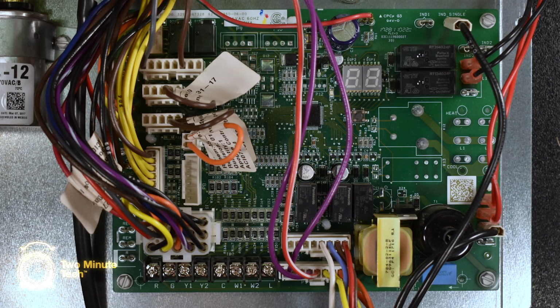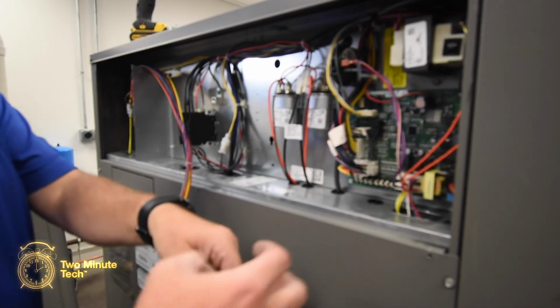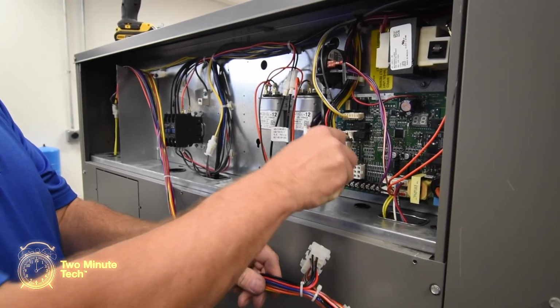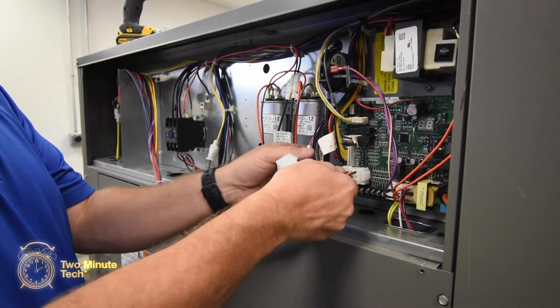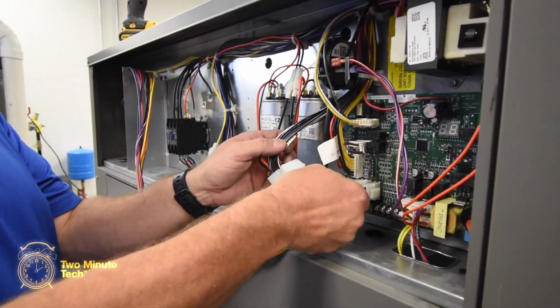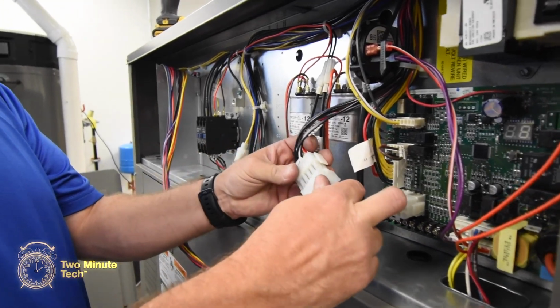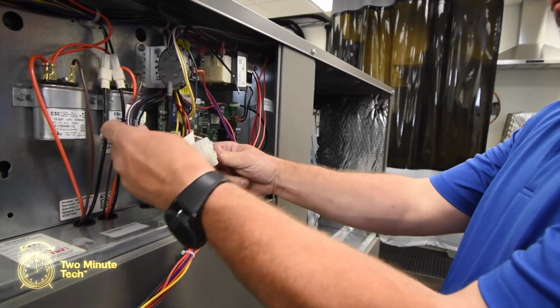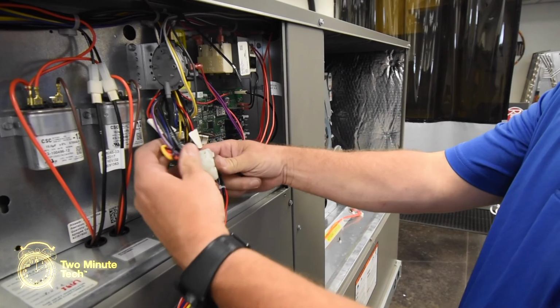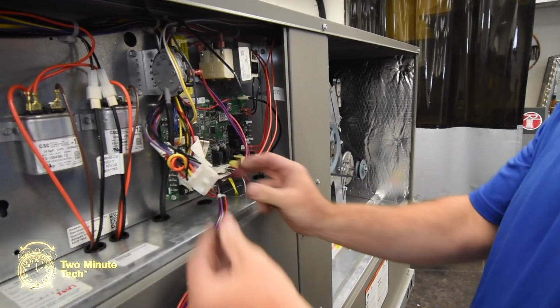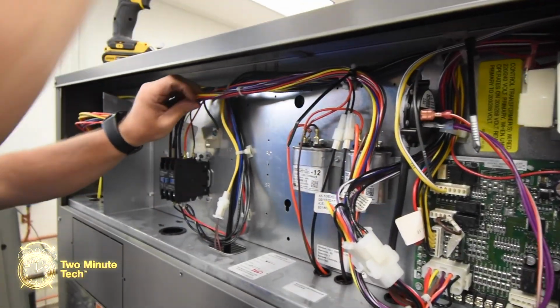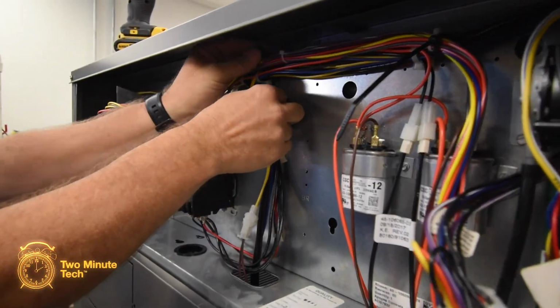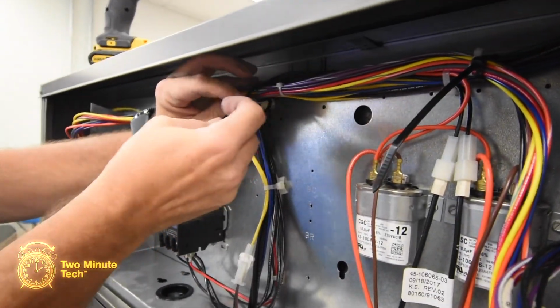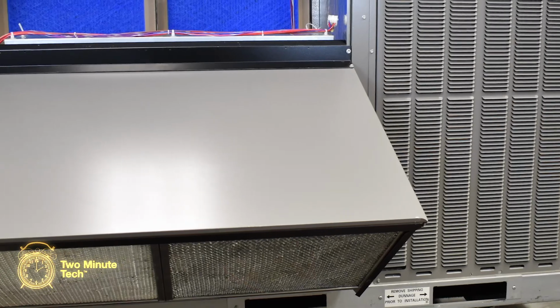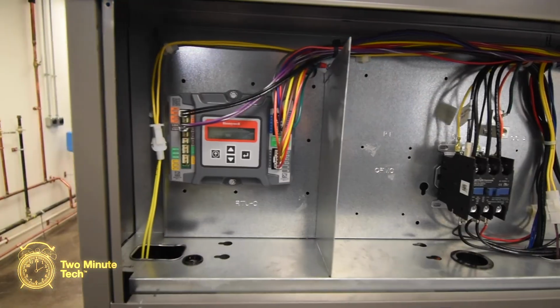At the main control board, on the right side of the control panel, locate and disconnect the 15-pin Molex connector for the economizer. Connect the 15-pin male Molex connector to the female connector on the main control board. Connect the 15-pin female connector to the 15-pin male connector that was removed from the control board. Using cable ties, secure the new wiring harness to the existing cables across the top of the control panel. The installation of the horizontal economizer is now complete.